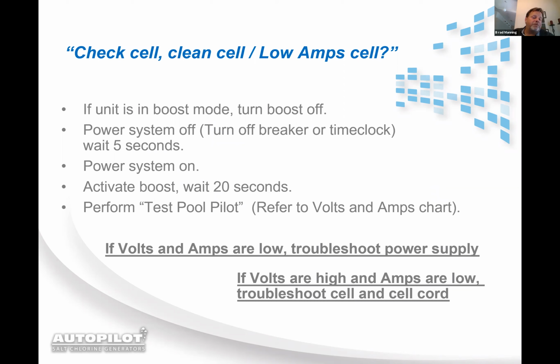If the unit is in boost mode, turn the boost mode off. This is how you do a proper test on a Pool Pilot. If it's in boost mode, turn the boost off. Power the system down. Power it back up again. Activate the boost when it comes out to the purifier screen. After activating the boost, you wait 20 seconds and then you do a test. After you do a test, it's going to give you the volts and amps on each one of the cells.